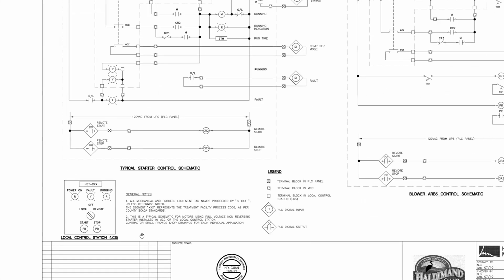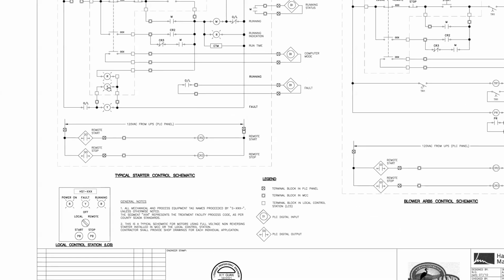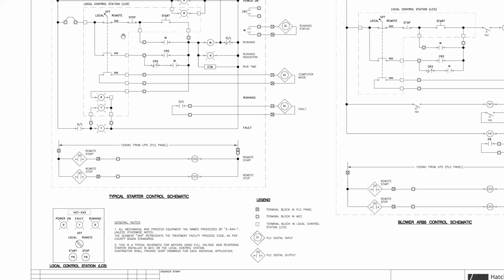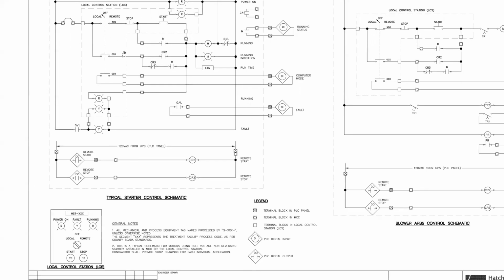Oh, here's a layout, a typical starter control schematic that shows power on, running, and a fault light. So even though here is showing multiple, this fault light, because it's in this box, exists on the local control station. And this one exists on the panel front here.